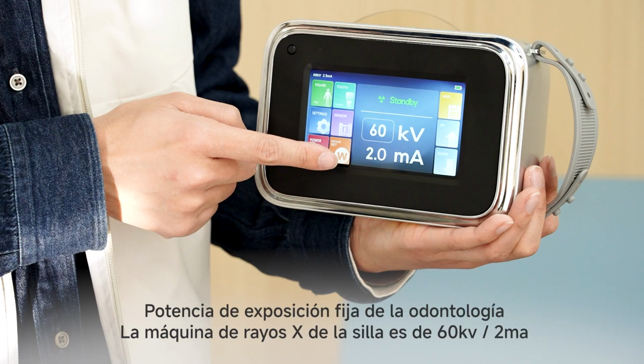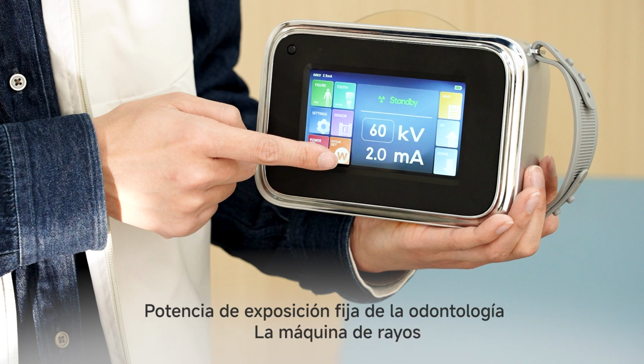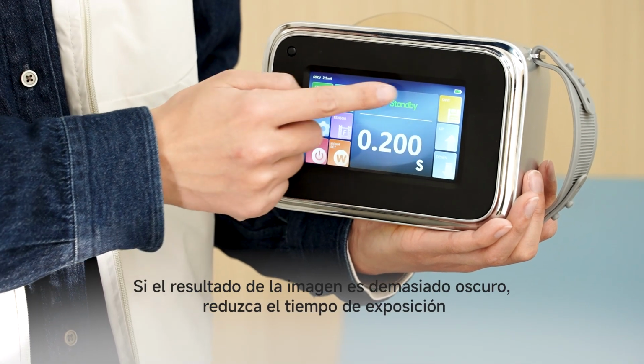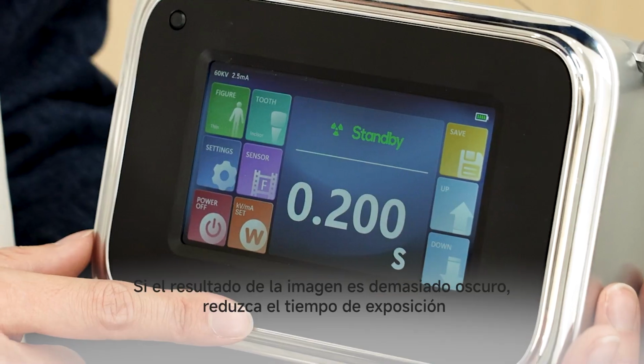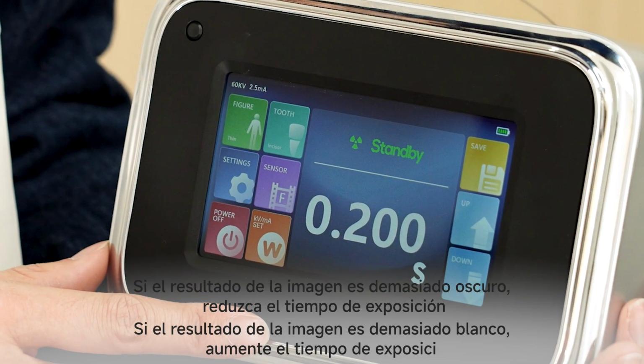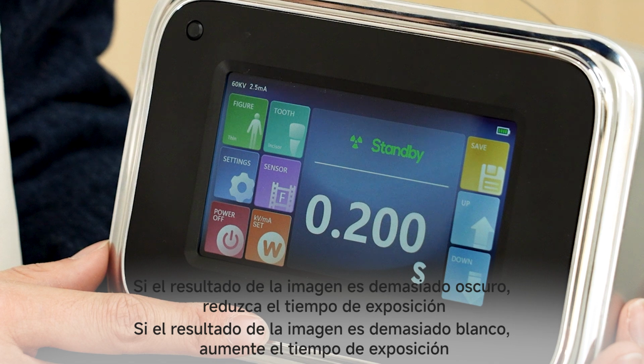The fixed exposure power of the dental chair X-ray machine is 60 kV and 2 milliamperes. If the image result is too dark, reduce the exposure time. If the imaging result is too white, increase the exposure time.